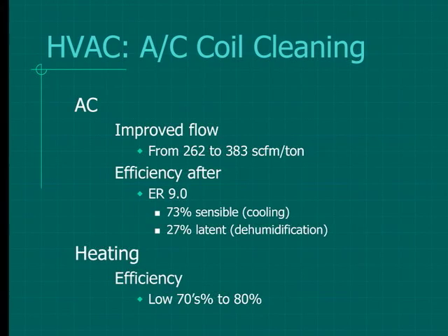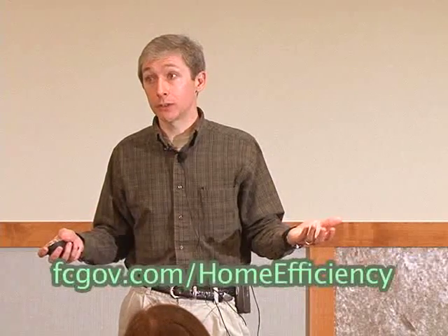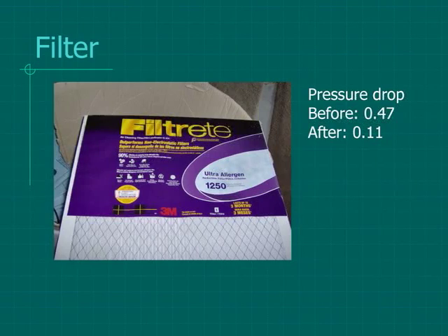So it's important, these things are systems. The furnace and the air conditioner and the ductwork, it's a system, they work together. They may have been installed by different contractors, but when those contractors put those two systems together, they need to check that interface and make sure they're putting the right size furnace, the right size air conditioner with the right size ductwork. Here's an example of another filter.